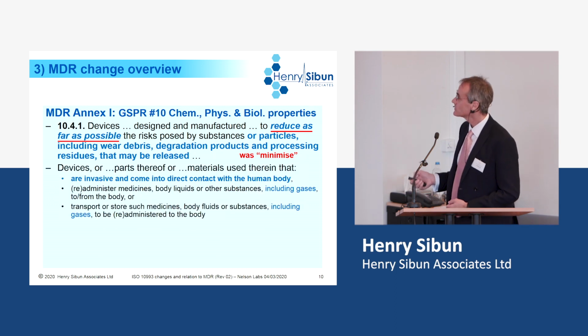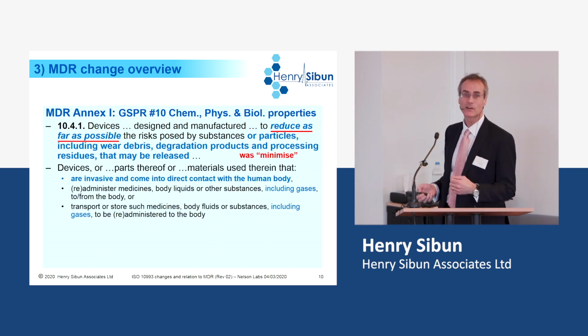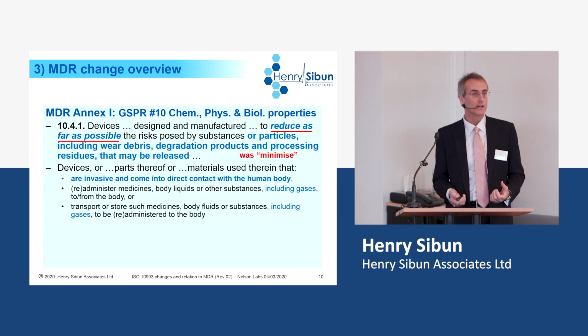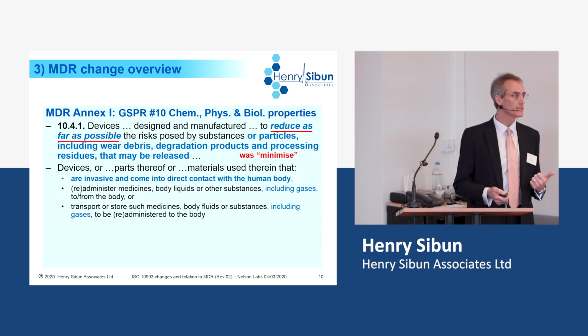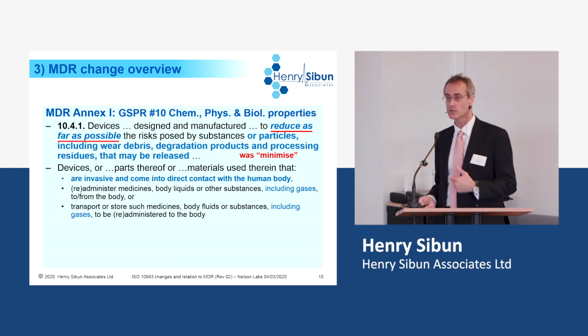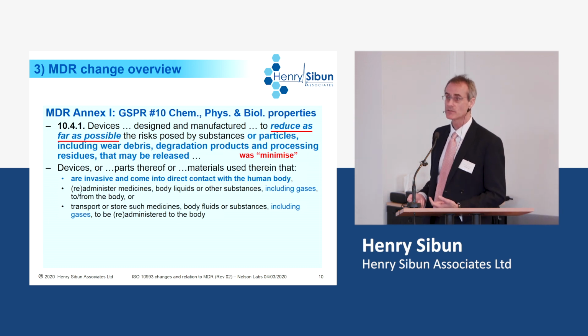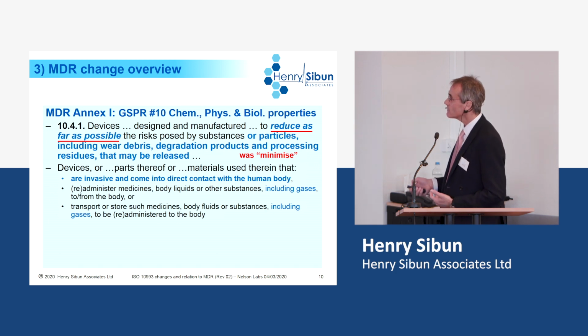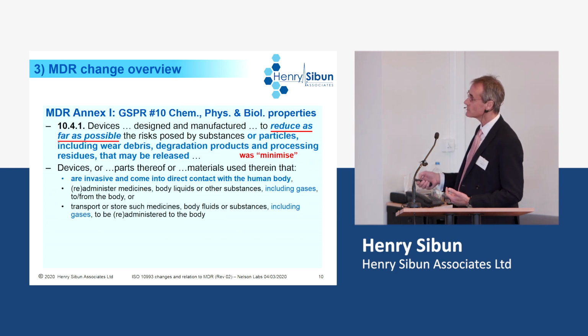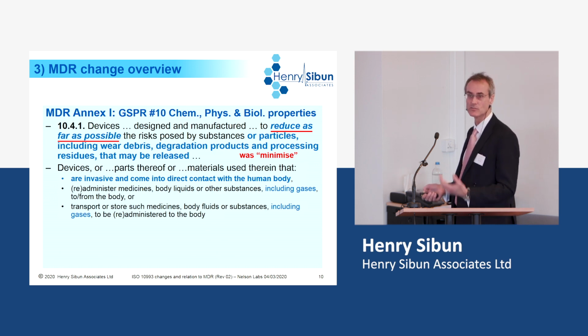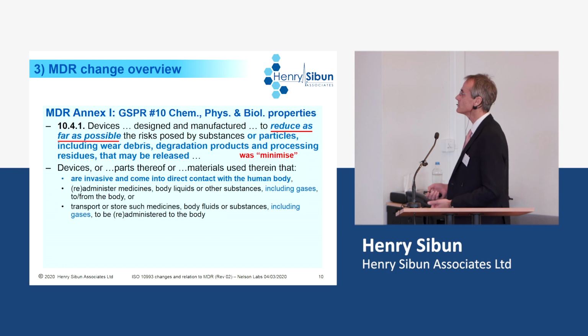It then goes on, so the special requirements for devices containing phthalates, for example, include risk assessment in the MDD. They include labeling of the device to warn the user, any special precautions if they're used on certain patient groups. And in the MDD, they cover devices for infusion and transfusion, like infusion sets, and things like blood bags for storing medicine, storing blood and tissue components.